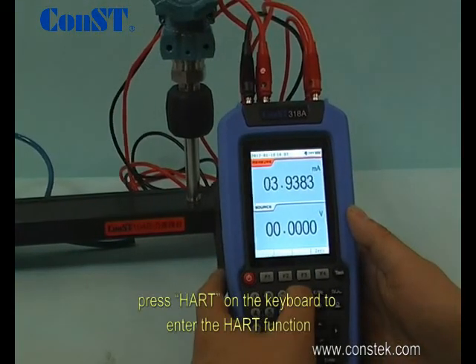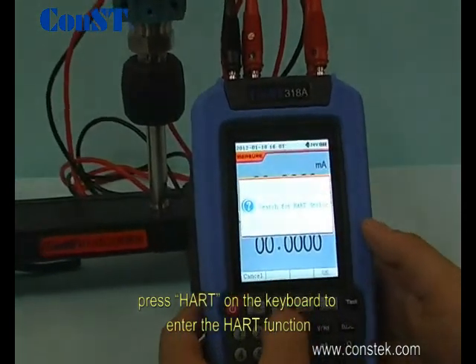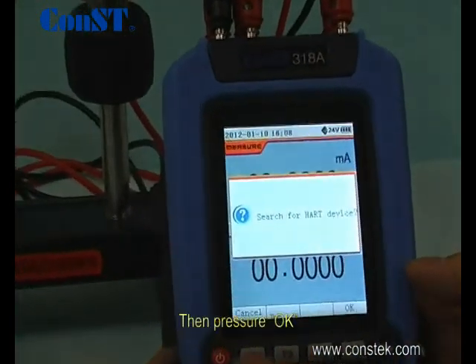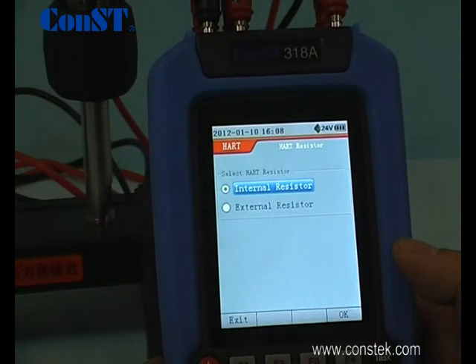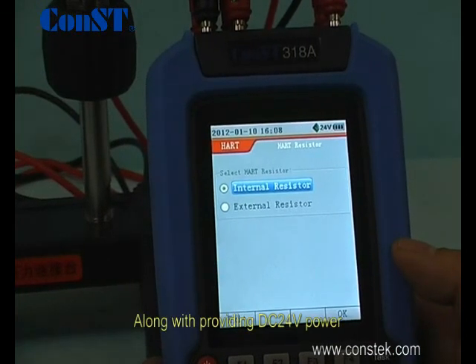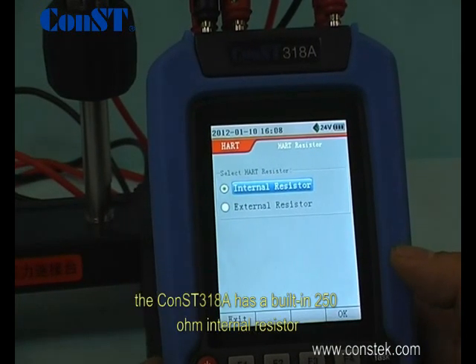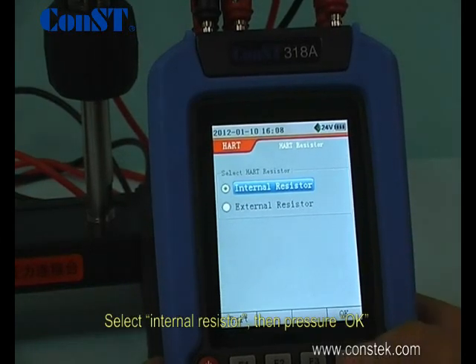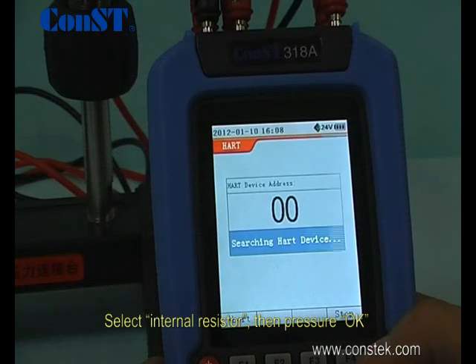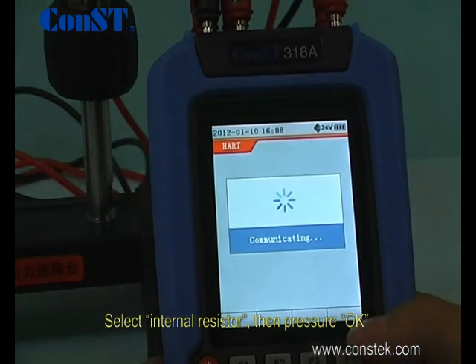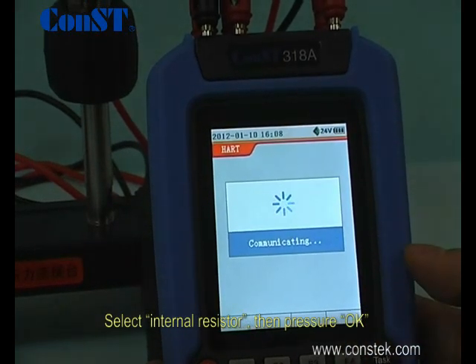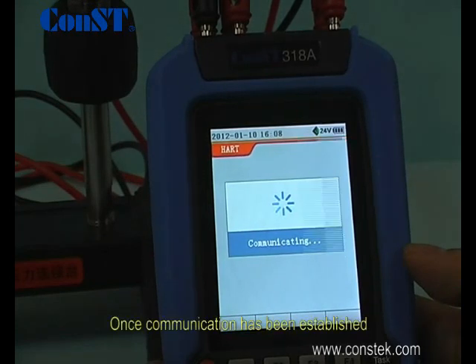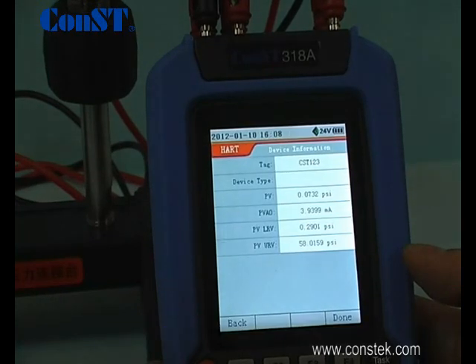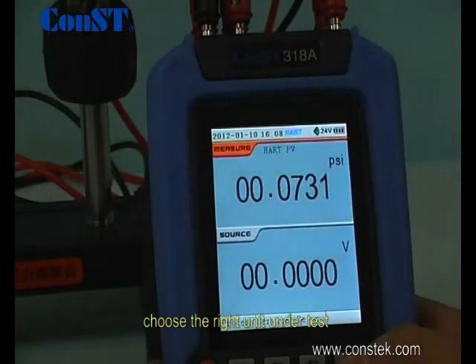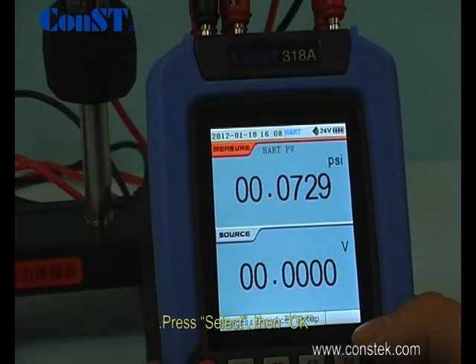After connecting, press HART on the keyboard to enter into the HART function, then press OK. Along with providing 24-volt power, the ConST318 has a built-in 250 ohm internal resistor. Select Internal Resistor, then press OK. Once communication has been established, choose the right unit under test. Press Select, then OK.